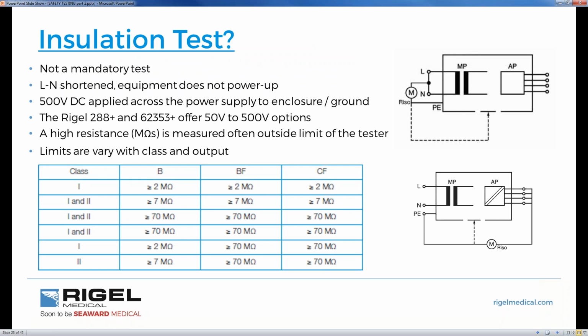Insulation test. What is an insulation test? It's not mandatory for 62353, but it's generally adopted in portable appliance testing in the UK and in end-of-line production testing with some of your high-pot testers that are used to validate electrical goods before they leave a factory. What happens is within the tester, the Rigel will short live and neutral together. So we drop a relay. If this is our medical device here, we drop a relay across live and neutral together to short it.